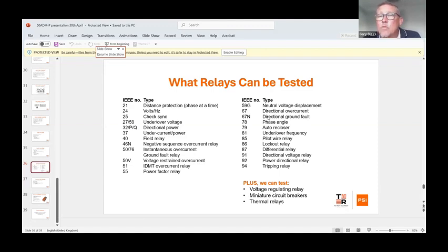Now, when you're looking at a relay, the data sheet of the relay will designate what the ANSI number of that relay is. The most common relays will typically be volts and frequency, which is number 24, and 27 and 59, which are under and over voltage relays. I can't find the current relays, but the current relays are undercurrent and power, 37. They're the most common ones that you're going to see. And then up with those will be directional relays, which are quite common these days as well. But the relays that we can test, we list out on our data sheet, so it's very clear. All you've got to do is look at your relay, see what ANSI number your relay falls under, check our data sheet, and it will tell you whether or not we can test that. Obviously, if you've got a 100 amp relay and you buy the 50 ADM-P, you won't be able to test 100 amps because it's only 50 amps, but it'll tell you the type of relay that we can test.